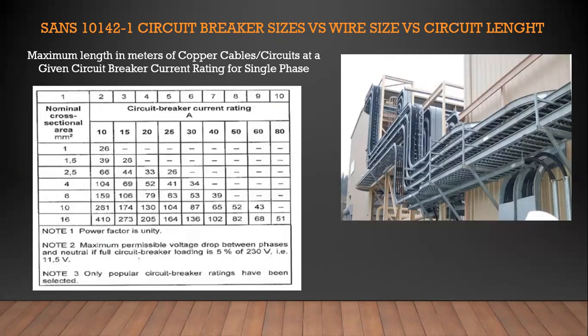I've also got a table in there from the wiring regulations on the maximum length of circuits, with the wire size in the left-hand side column versus the circuit breaker rating. So this is easy for you to determine. If the geyser is supplied by a 20 amp single phase circuit breaker, you look at the wire and determine that it's a 2.5 wire. The maximum length of this circuit should be 33 meters. So if the geyser is situated, for example, 60 meters away from the DB board, with a 2.5 wire and a 20 amp breaker, it's not legal, and hence you'll get a huge voltage drop.